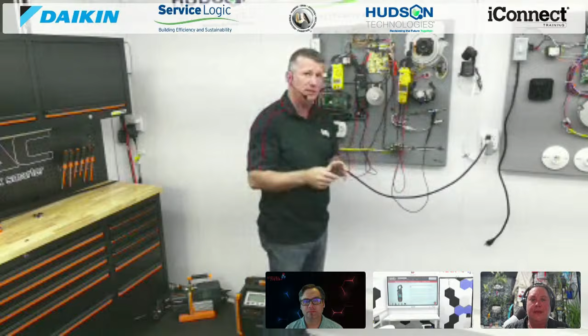So let's add a fan to this. Now I'm up to 0.5 volt AC that I've grabbed from the 27 watts we're using in this circuit. As technicians out in the field, sometimes we'll find these ghost voltages and not know exactly where they're coming from. When we take the time to understand that our meter is reading voltage, and understand where that voltage is coming from, it'll change our perspective on how we use our meters.